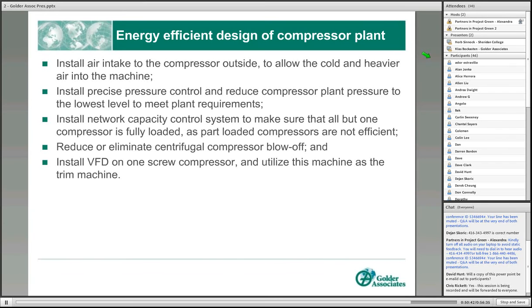And just the last slide, I just wanted to highlight a few things that will affect the efficiency of the system in addition to what we've spoken of so far. It's also useful to have the air intake to the compressor located outside, because in cold winter day-like weather, you are much more effective compressing air from a very cold temperature with more mass. The machine is going to be more efficient, and you will get more CFM per brake horsepower with an outdoor installed air intake.